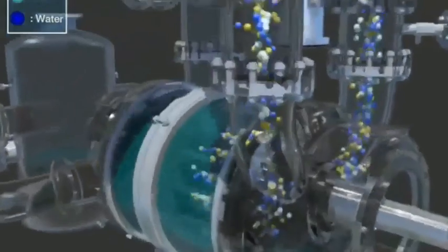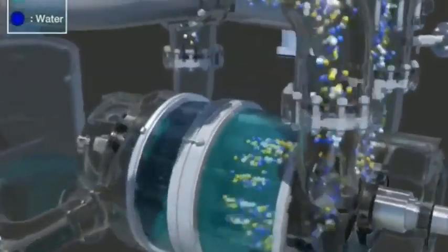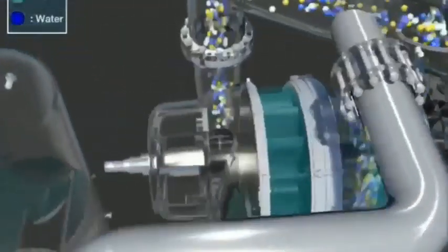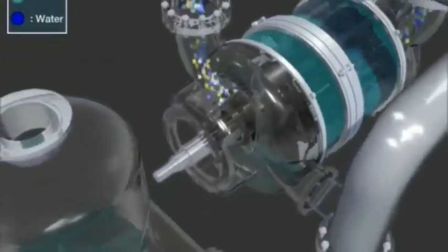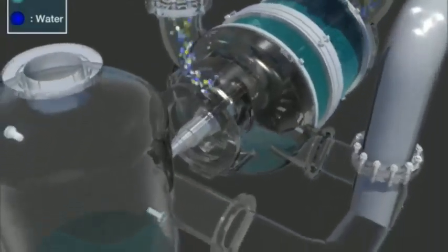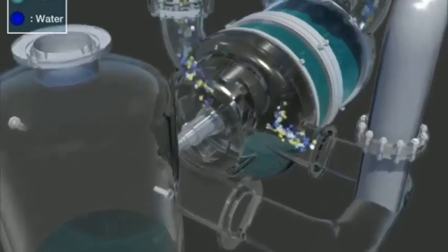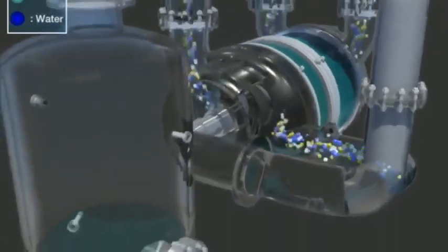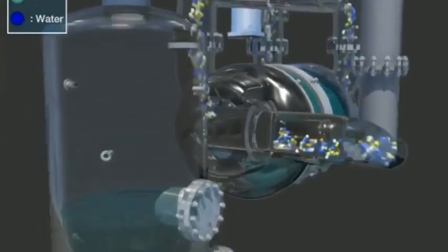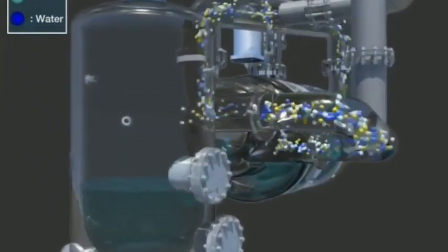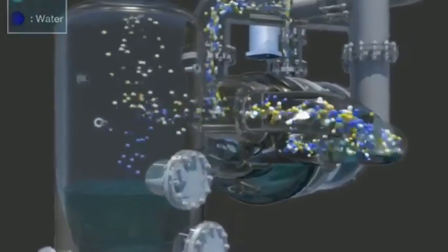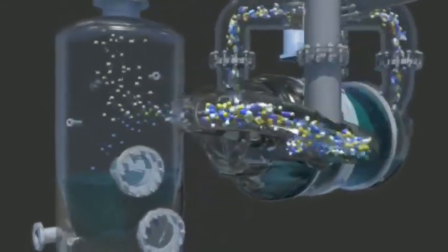The air emitted at the first stage goes into the second stage suction through the interstage crossover and is emitted to the separator tank by the same process as the first stage. The mixture of air, gas, and liquid sent to the separator tank gets separated to emit the air and gas and recirculates the seal water.